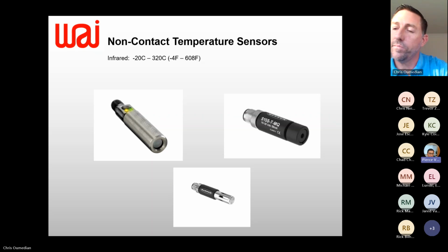Yeah, for the class, I'll just briefly describe this application. We're having many, and when I say many, probably a dozen in the last 2 months, end user customers contacting me regarding problems with condensation inside electrical enclosures. And it's not just along the coast. The wide temperature ranges in the desert will do this also. And the definition of dew point is the combination of temperature and relative humidity. Above the curve, you're fine. Below the curve, you start getting condensation.